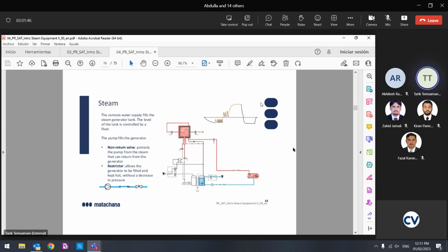So the steam generator cannot give us continuously, I am talking continuously, steam enough to reach the jacket, to fill the jacket and chamber to the maximum pressure. Sometimes we can get to this threshold. That is the point. For these points, I have to wait a little, about 15-30 seconds. Then I continue the rest of the pressure injection to reach the maximum. Then when I reach the maximum, I stop this valve.